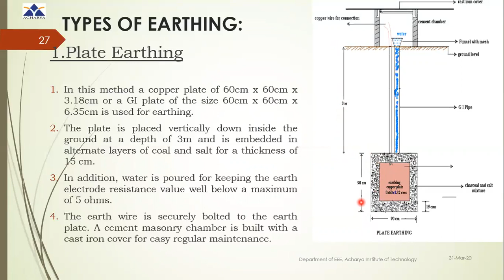The effectiveness of this type of earthing increases with increase in plate area and depth of embedding. The only disadvantage of plate earthing is that the discontinuity of the earth wire with the plate below the earth cannot be observed physically. That is, if the earthing is not proper, maintenance is very difficult since this plate is deep inside the earth. Also, if the soil resistivity is very high, even then the earthing will not be effective.